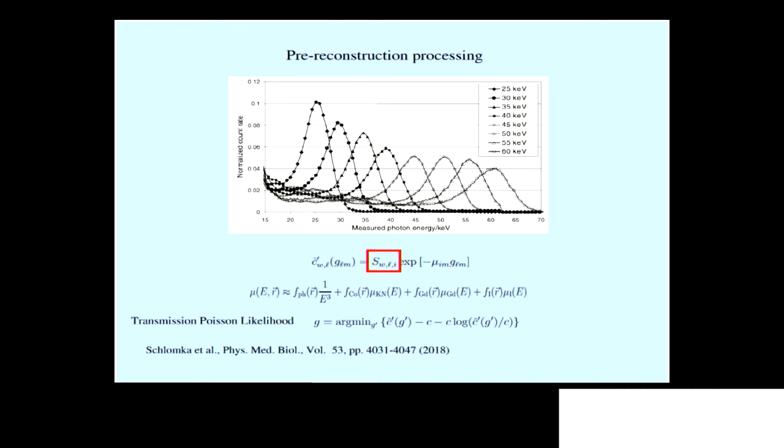One of them is that the charge from one pixel can get split amongst a couple of pixels. So it doesn't only hit the one. That's called charge sharing. And then it's actually detected in a lower energy window, and that's why you see these long tails.